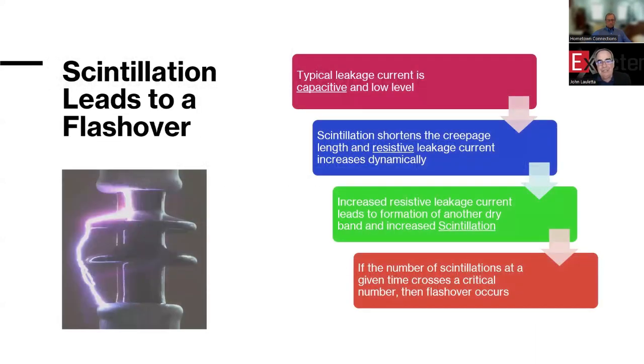It's a process called scintillation, and I'm just going to walk through it very quickly here. But typically, there's always a capacitive leakage current from every device to ground, even the wires to ground. And that's just because of the dynamics of the AC electrical system. But when the scintillation shortens the non-conductive path of the insulator itself, now you have a high resistive leakage current. That high resistive leakage current is going to find its way to ground through your wood poles.